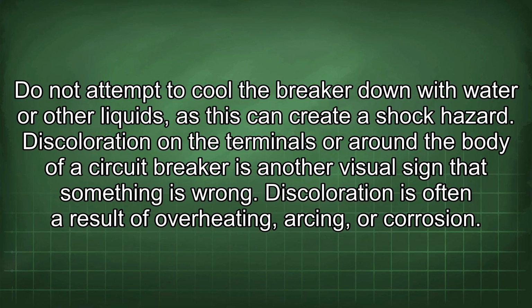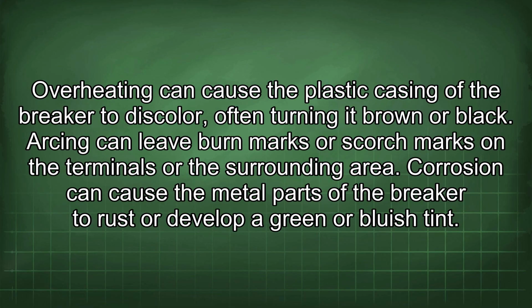Discoloration on the terminals or around the body of a circuit breaker is another visual sign that something is wrong. Discoloration is often a result of overheating, arcing, or corrosion. Overheating can cause the plastic casing of the breaker to discolor, often turning it brown or black. Arcing can leave burn marks or scorch marks on the terminals or the surrounding area. Corrosion can cause the metal parts of the breaker to rust or develop a green or bluish tint.